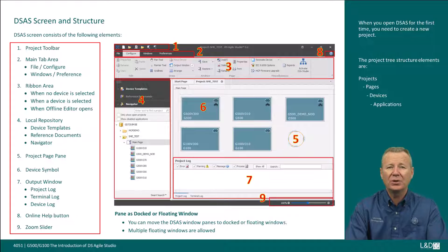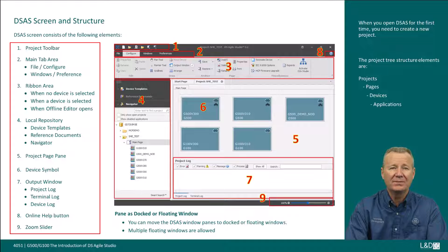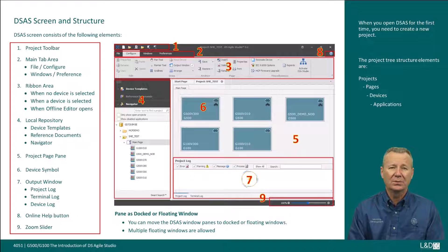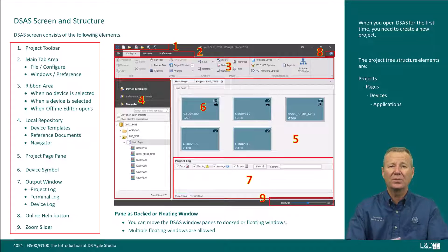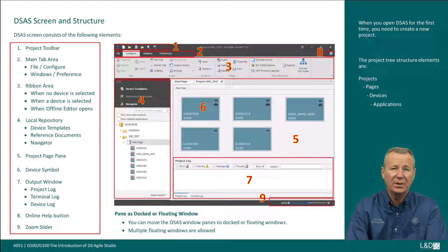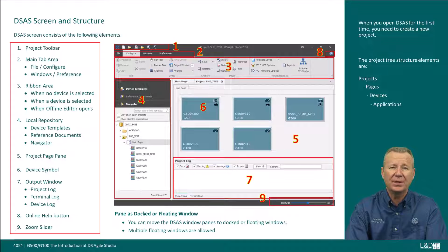The project page pane is a project container used to group devices into convenient collections within the project; typically each page represents a substation bay. A device is defined as a piece of equipment and its configured firmware, and a device always belongs to a project. The output window allows you to view the project log, terminal log, or device log; you can toggle checkboxes to reduce displayed information and search for specific text.